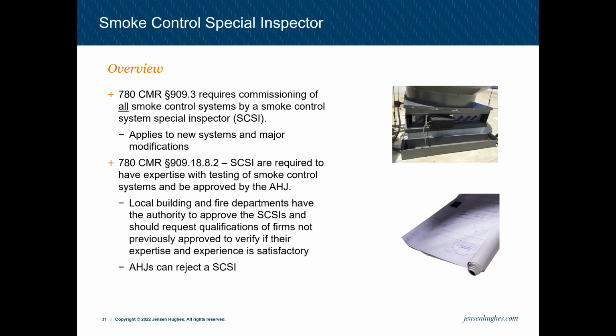Special inspection is required to have expertise in smoke control and be approved by the AHJ. The AHJs can reject a smoke control special inspector if they think the person is not versed or not experienced in the area that they're working on. Smoke control special inspection does not take the place of an AHJ. Instead, it's there more for special items that might be beyond the area of expertise of an AHJ, or might be very laborious, that AHJs don't have the time or bandwidth to support. It's something that requires more review.